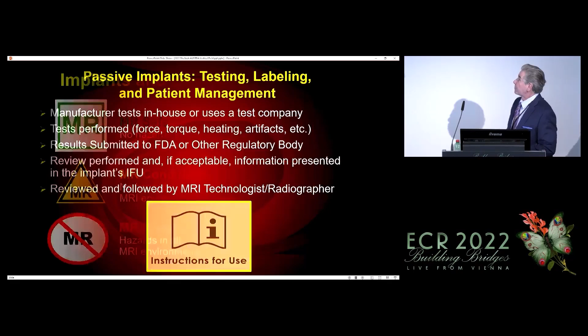The manufacturer of the implant either does in-house testing, so they've hired medical physicists and bioengineers and those with a body of knowledge with regard to doing proper testing, or they engage in outside companies such as the one I'm the president of. Then the tests are performed for passive implants. We assess force, torque, we characterize artifacts, and we test MRI-related heating at a specific field strength and frequency. And by and large, that's always at 1.5 and 3 Tesla. And the reason is those are the predominant MR systems that are used in the clinical setting. So invariably, you will see labeling at 1.5 and/or 3 Tesla only, especially for passive implants.